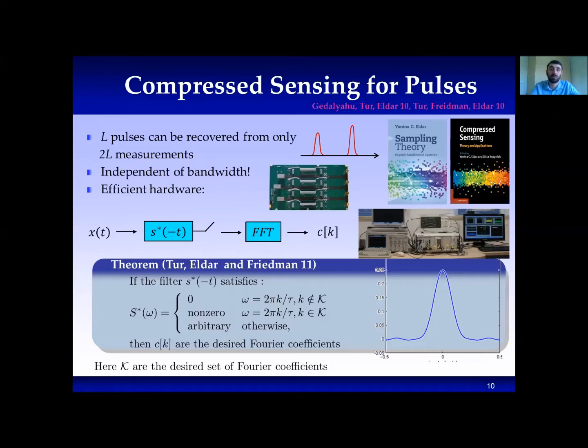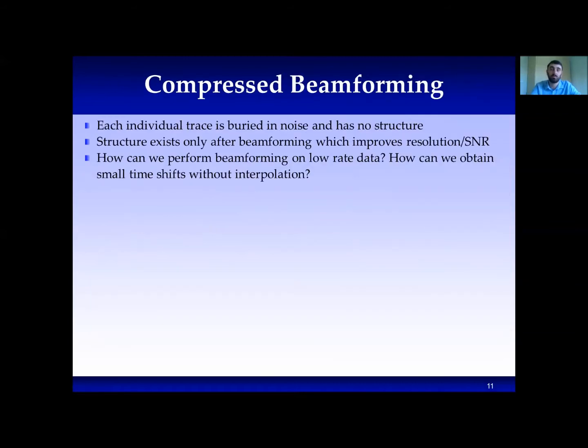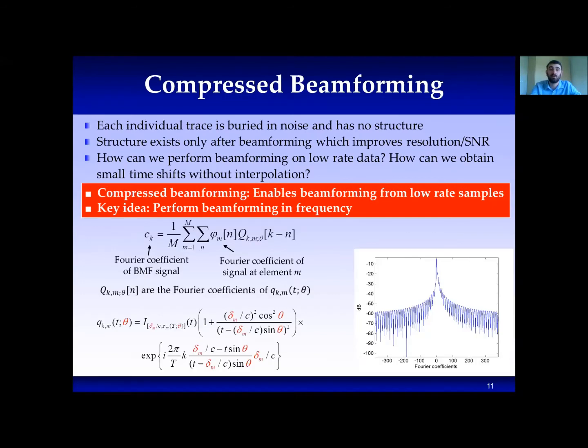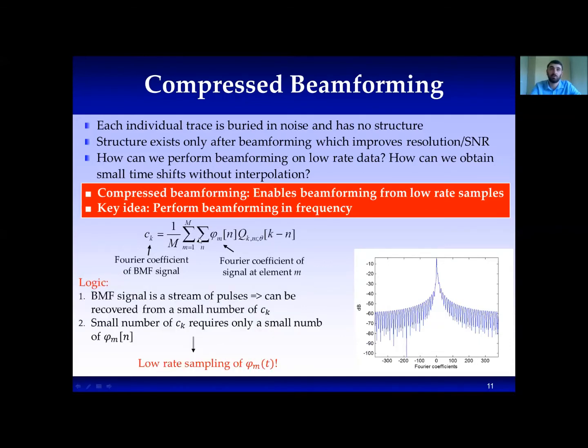Here we encounter another problem: how can we perform beamforming without interpolation on the subsampled data? How can we recover the signal from its subsampling? The answer is that we do it in the frequency domain. Based on the subsampled frequency coefficients, delay is applied in frequency using a fast decaying distortion function. The beamformed signal, which is a stream of pulses, can be recovered from a small number of coefficients, resulting in low sampling rate at each element. The Fourier coefficients phi_m at each element are multiplied by q, the distortion function that applies the delay, and after summation we obtain the Fourier coefficients of the beamformed signal.